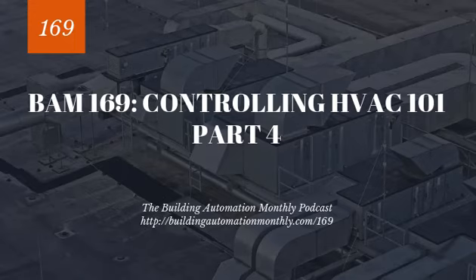And finally, condensate. So whenever you transfer heat from steam, you have a phase change that causes it to condense back into its liquid form. This is natural. It's okay, but it needs to be controlled. You have to remove the condensate from the piping, and you typically will do that using a condensate pump at the bottom of the coil or at the heat exchanger. This will remove that condensate, and it will make sure that you don't have condensate buildup, which will lead to wet steam, which will lead to bad heat exchange, which is just all corrosive and all sorts of bad stuff, right?